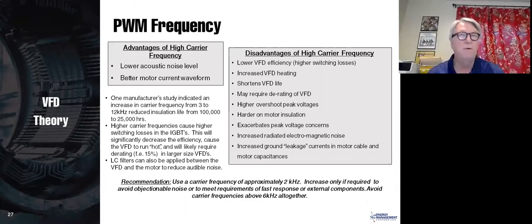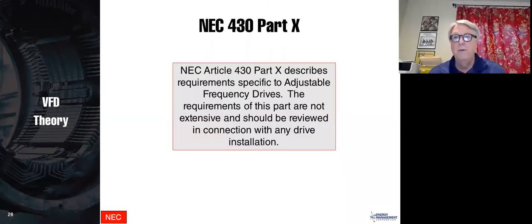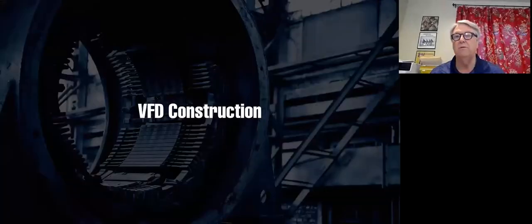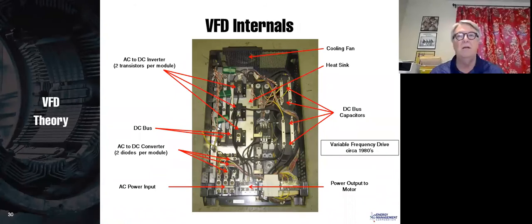The other thing is if you have a filter on the output, like maybe a sine wave filter, and the sine wave filter manufacturer states the output frequency must be 5 kilohertz, well, then you do that. You follow their recommendation. This is NEC 430 Part X. That is the part that covers variable frequency drives. Now let's look at a real VFD.